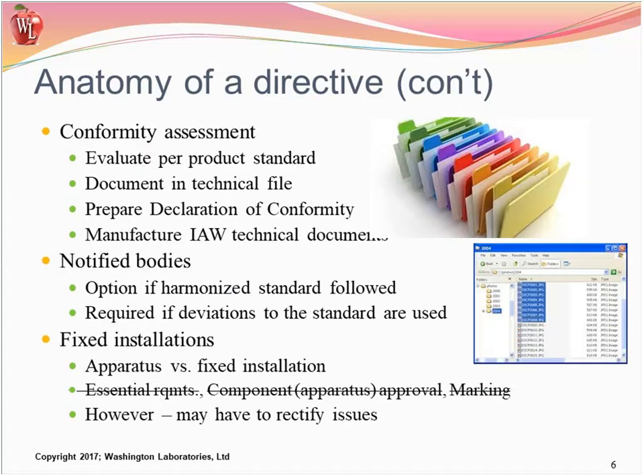The directive continues to say I need to get a conformity assessment. Now, that doesn't necessarily say I have to test. It says I've got to evaluate the product. Testing may or may not be applicable. You need to document these in the technical file associated with the product and prepare your declaration of conformity.